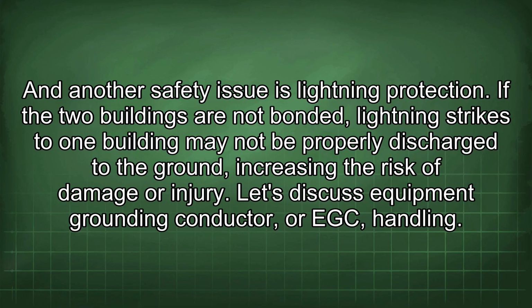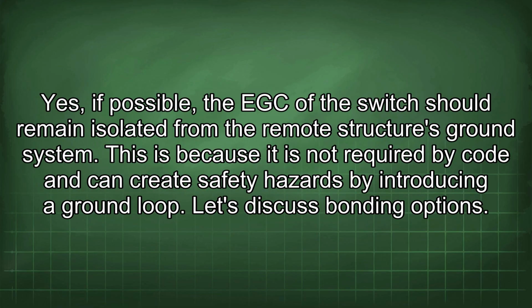Let's discuss equipment grounding conductor or EGC handling. Yes, if possible, the EGC of the switch should remain isolated from the remote structure's ground system. This is because it is not required by code and can create safety hazards by introducing a ground loop.